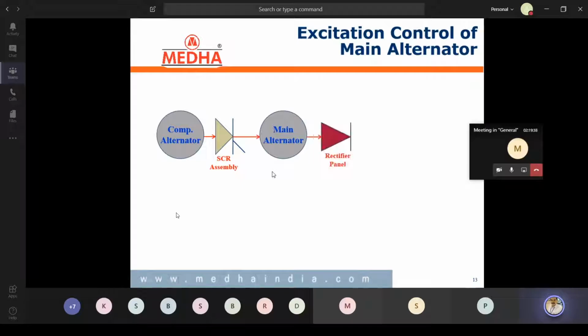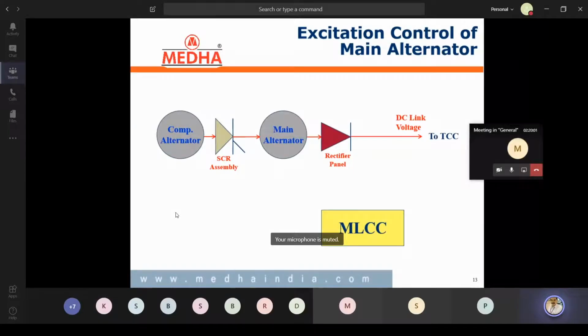Then the main alternator generates 3-phase AC, again internally to left bank and right bank. Each path provides 3-phase AC that goes to separate rectifiers, and both rectifier outputs are connected in series, and finally this becomes the DC link path. This DC link will be given to the TCCs and the different brake chopper paths and all.